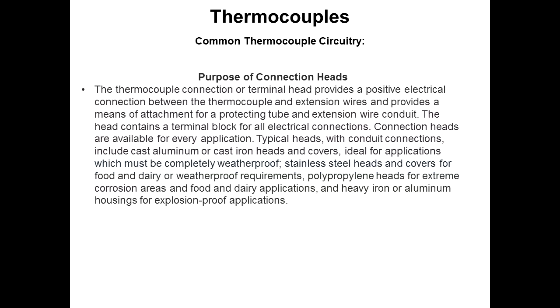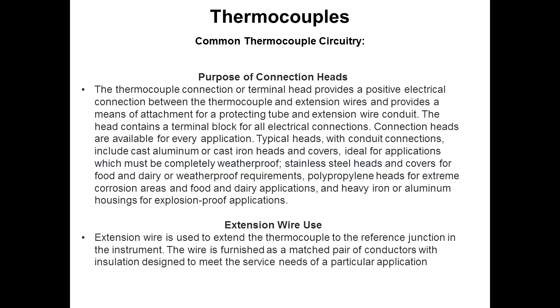The connection heads are available for a lot of different applications. We have conduit connectors where you can run your wire back through conduits and protect them. We have cast aluminum, cast iron with aluminum covers or cast iron covers. These are weatherproof areas. We have stainless steel heads and covers for food and dairy or weatherproof requirements. Polypropylene for extremely corrosive areas or also other food and dairy applications. And then heavy iron or aluminum housings for explosion-proof applications. Extension wire, we can supply that on rolls if you need that to go with a particular probe.